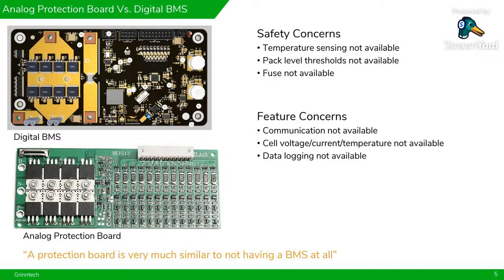The protection board is very similar to actually not having a BMS at all. It's only similar to the first generation of BMS, which more or less only did cell balancing, since there's only cell over voltage and under voltage protection - and even that has no redundancy, so it's very possible it will fail and you'll be in trouble.